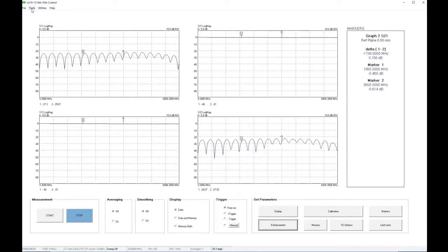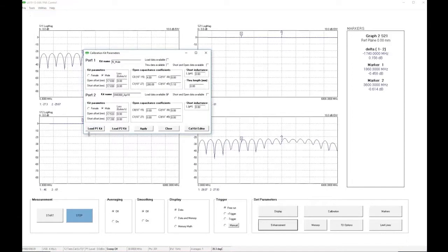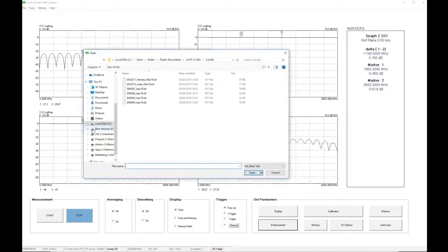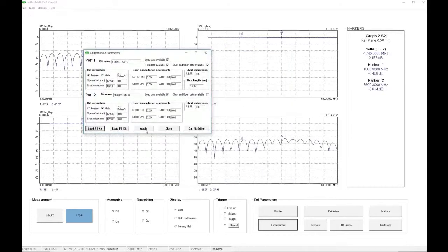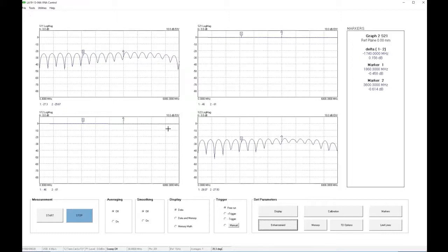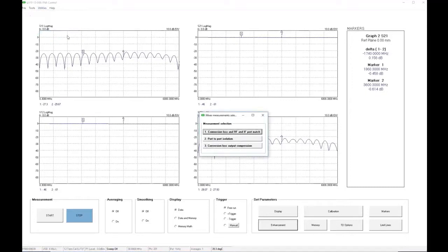Next thing we want to do is to select the calibration kit that we're going to use, and I know we're going to need a female kit, and we have the serial number 844 here with me, so I'm going to select that and apply. Close the form, and you're ready to use that kit now. Now we need to go to the mixer measurement menu. So that's under Utilities. We select Mixer Measurements, and we're presented with a choice of 3 types of measurement.